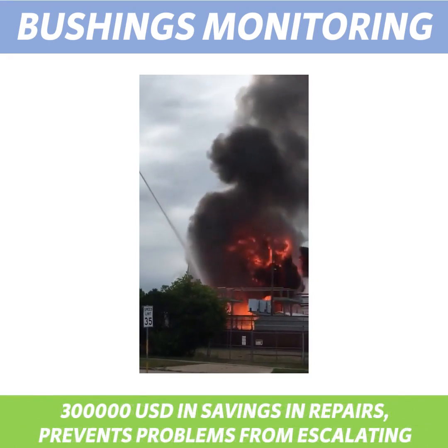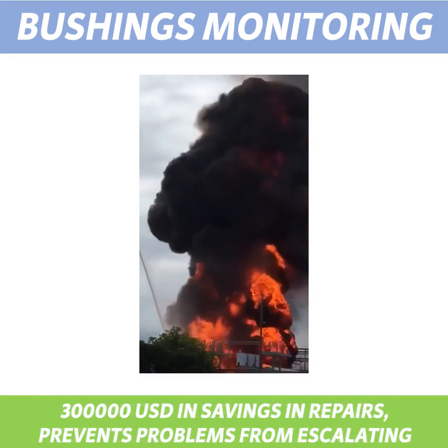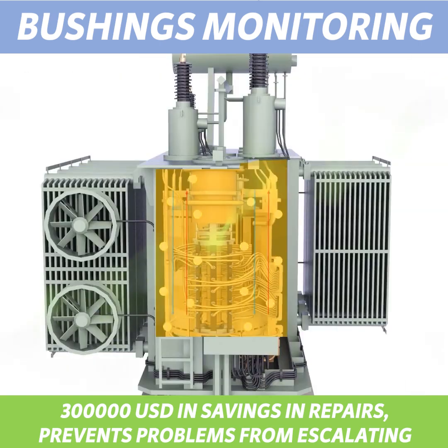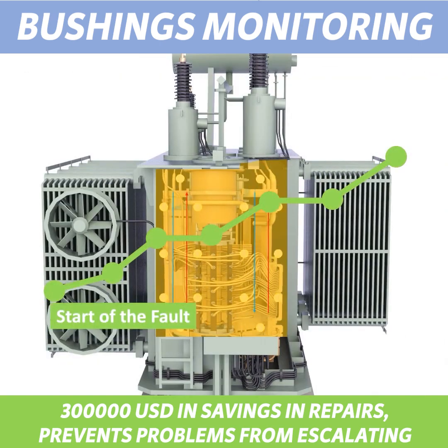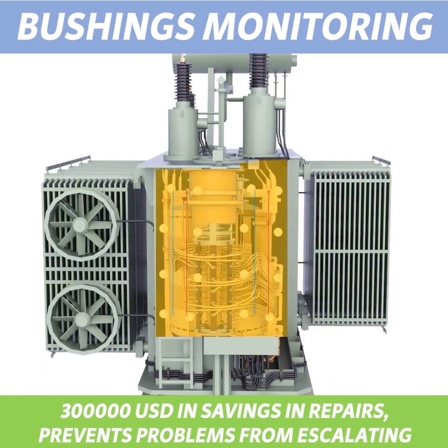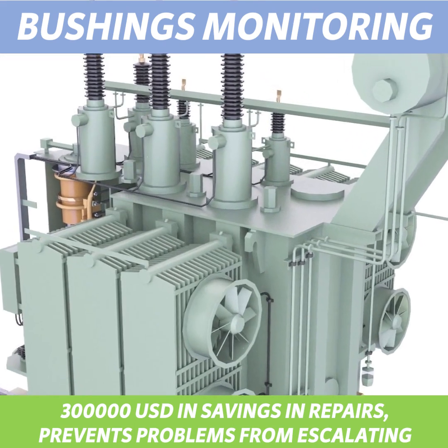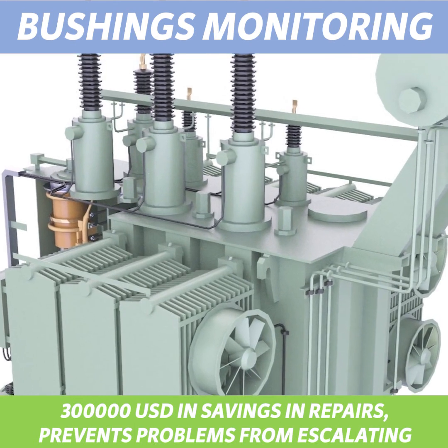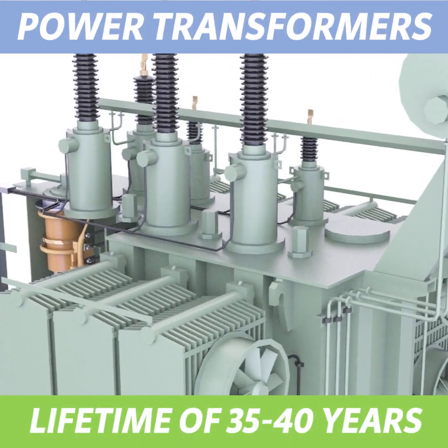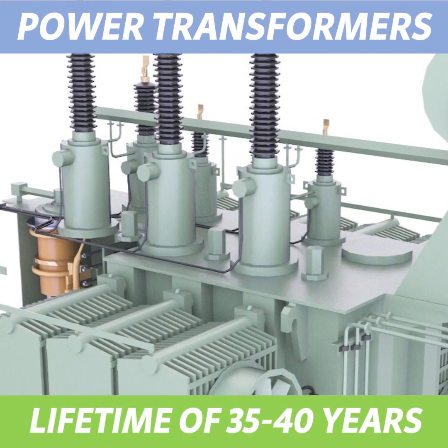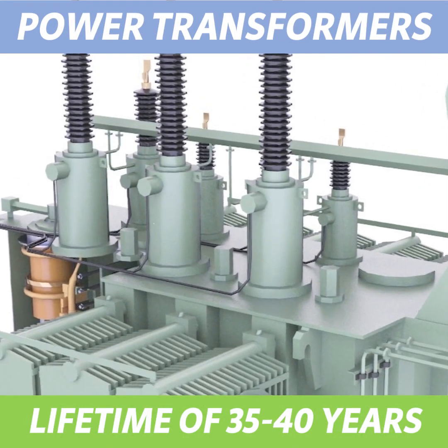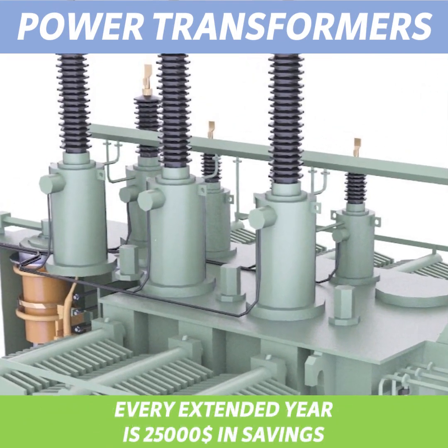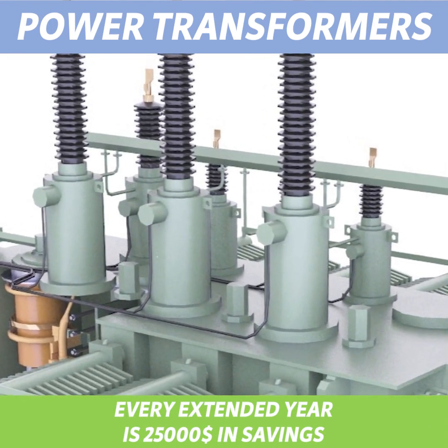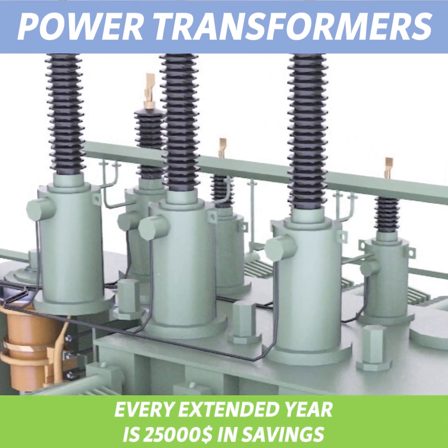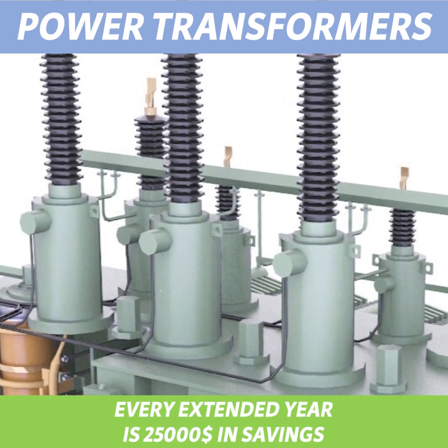US savings. Faults can happen in any phase of the bushing life cycle, but bushing monitoring will help prevent a problem from escalating. It can turn a catastrophic failure into a relatively cheap repair, saving min $300,000 US on repair cost, due to early fault indication. Power transformers are an asset with a typical lifetime of 35 to 40 years. During this period, its value gets amortized, $1 million US transformer price. This simply means that every year of lifetime extension is a saving of min $25,000 US.